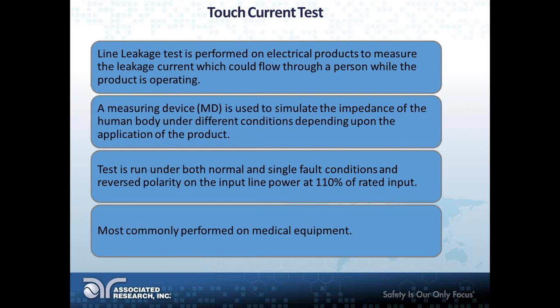Line leakage test is most commonly performed on medical equipment. However, we have seen applications where this test is performed on products that are not medical.